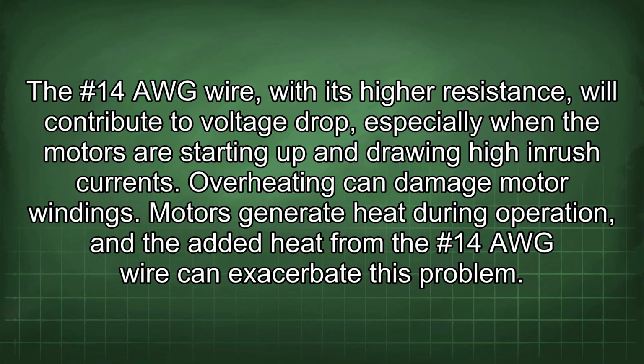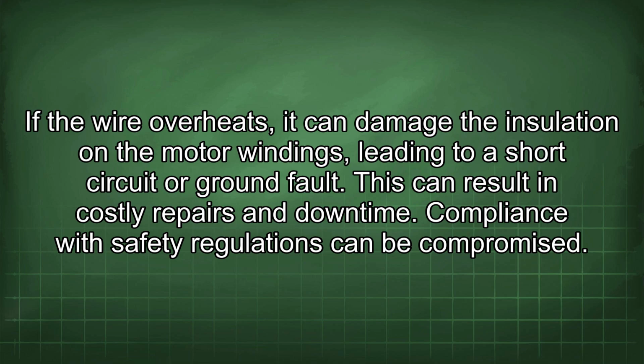Overheating can damage motor windings. Motors generate heat during operation, and the added heat from the #14 AWG wire can exacerbate this problem. If the wire overheats, it can damage the insulation on the motor windings, leading to a short circuit or ground fault. This can result in costly repairs and downtime.